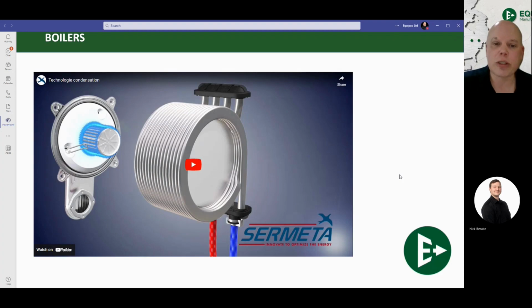Now this next one is going to be your water tube heat exchanger. On the left, that's our burner and our plate. On the right of that picture, that's our actual heat exchanger. That's where the water is going to be coming in from. One thing to note is that to create a water tube heat exchanger, they've taken a 3/4 inch round tube and ovaled it. So it creates a higher head loss, meaning that it has to be piped in a certain way to overcome the high head loss of the boiler itself.